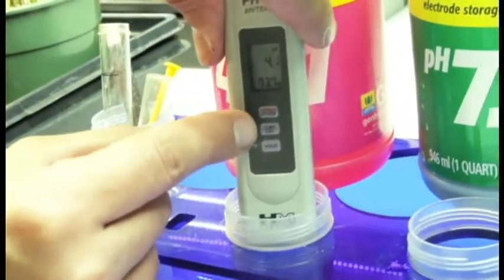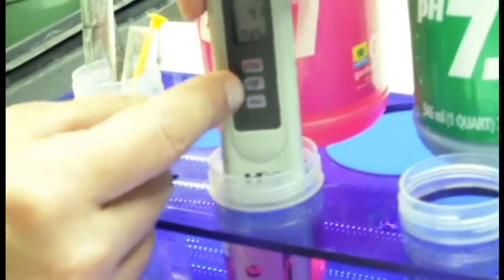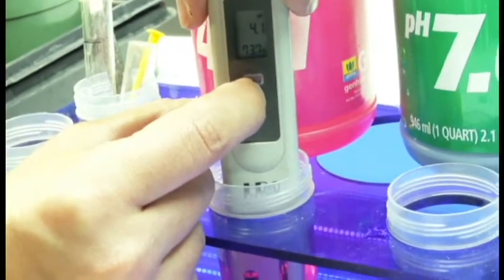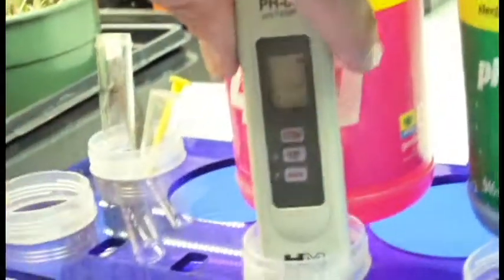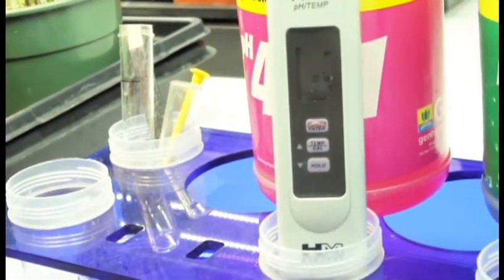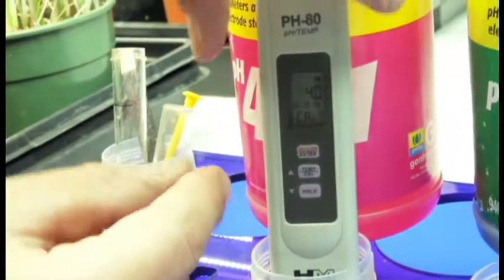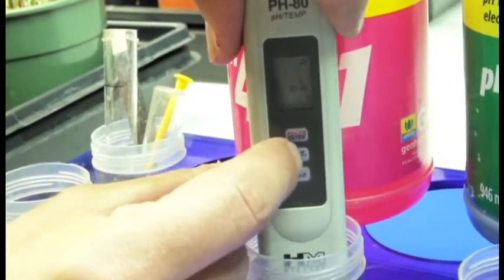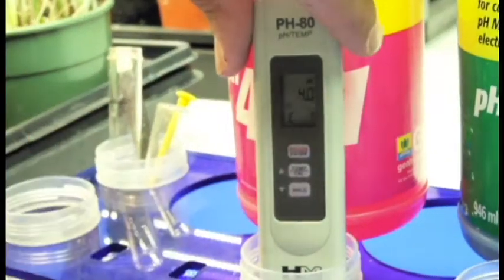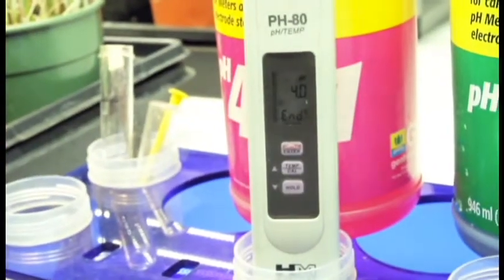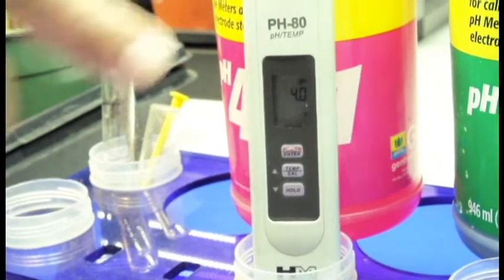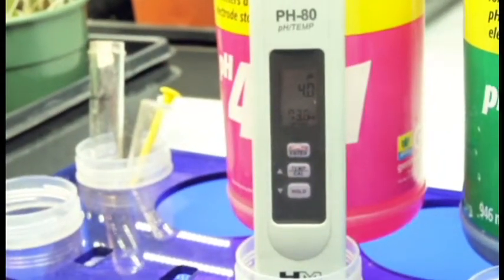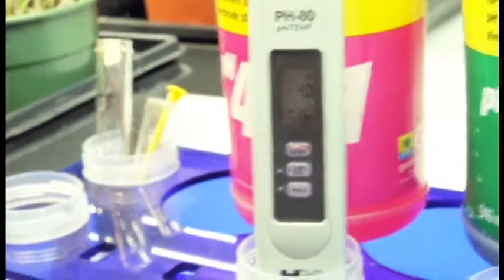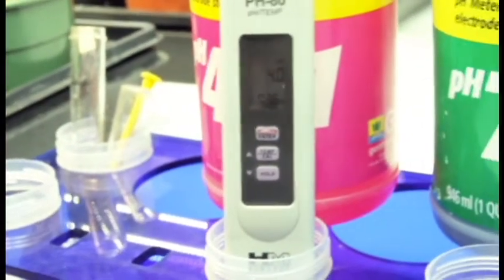So I'm going to hold down the center button that says temp/cal. I'm going to hold this button down until the meter starts blinking at me. There we go. It's saying cal and it's blinking 4.0 because it auto detects the solution it's in. If for any odd reason that's the wrong one, you can tap this center button again. It started calibrating before I could do it. I'll explain that on the 7.0. Give me just a moment. So it says end. Now that end is over, I'm going to hit the center button again and it goes back to Fahrenheit. That's how you switch between Fahrenheit and Celsius. Now it's calibrated at 4.0.